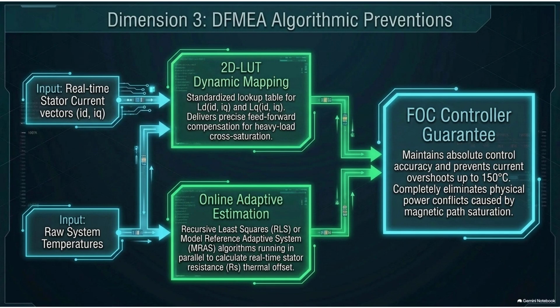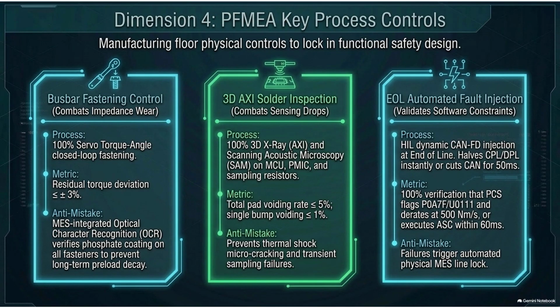And after the perfectly coated bolts are tensioned and the X-rayed circuit boards are integrated, the fully assembled power control system reaches the end-of-line, or EOL, test stand. And this isn't just a passive diagnostic check, right? They intentionally subject the unit to targeted fault injections to prove the 60-millisecond architecture actually functions in reality. Right. They simulate the absolute worst-case digital scenarios right there on the factory floor. So the automated test equipment might digitally sever the CAN communication lines, simulating a total BMS blackout, or instantly drop the simulated power limit to 0.